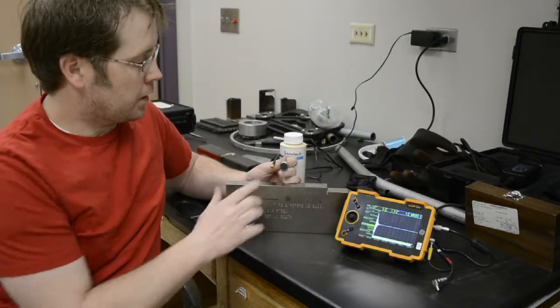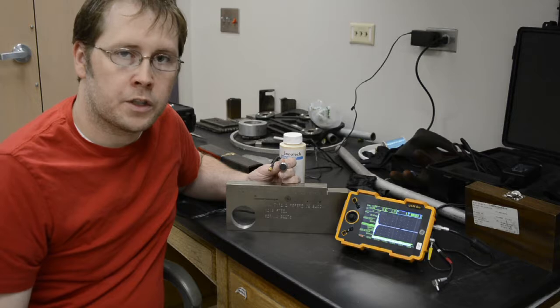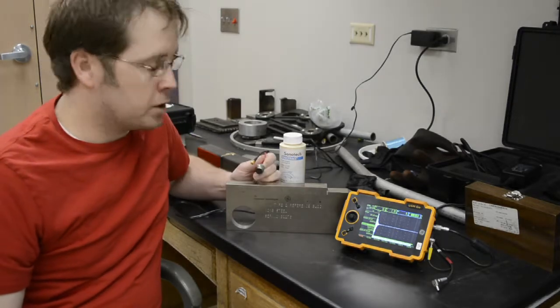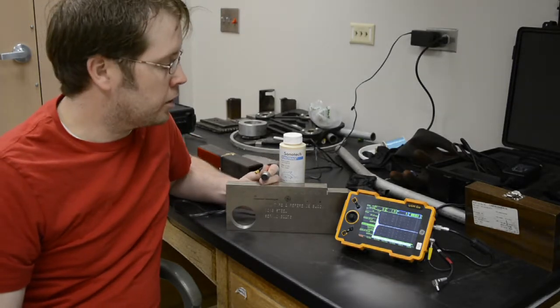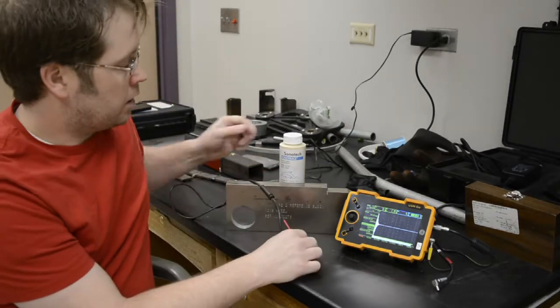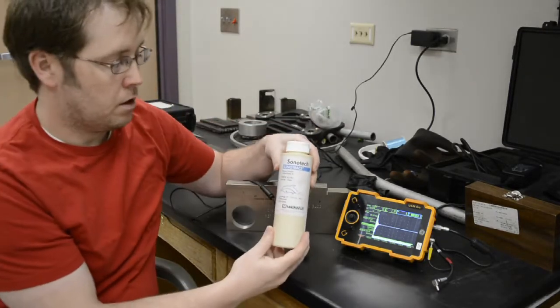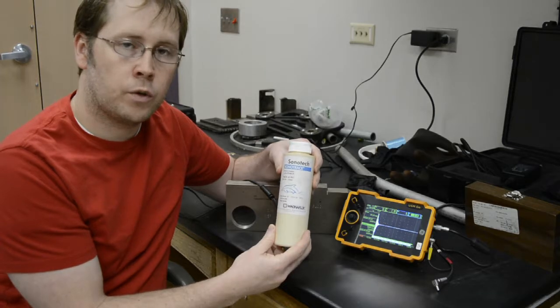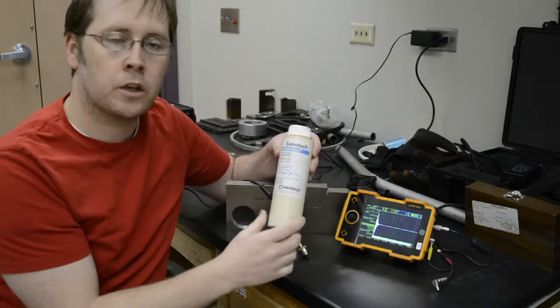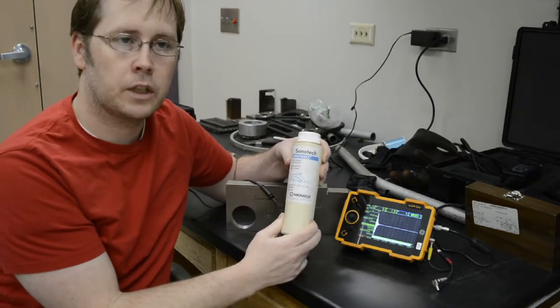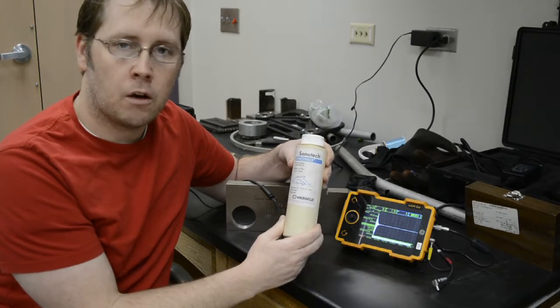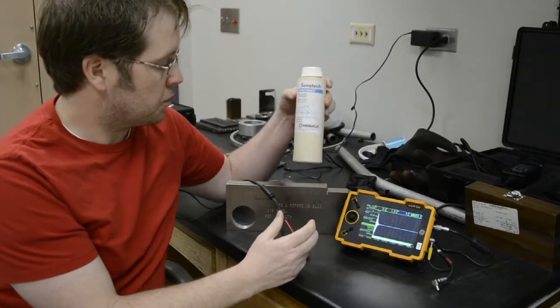Now, the surface of this transducer, of course, is not perfect, nor is the surface of the material that you're going to be testing. So that whenever you're testing, you're going to need a gel couplant on the surface of the material in between the transducer and the material to act as a transmission medium for the sound waves coming from the transducer.